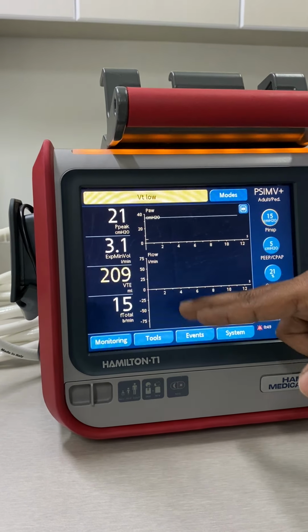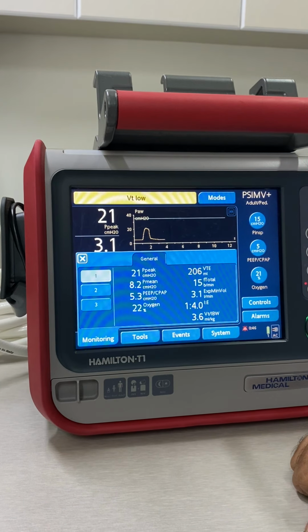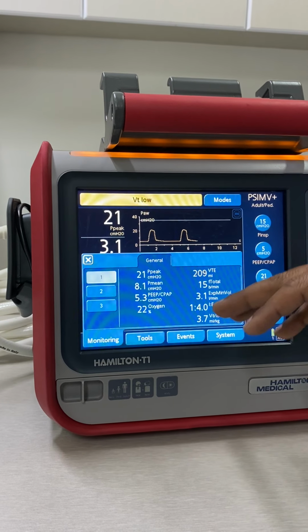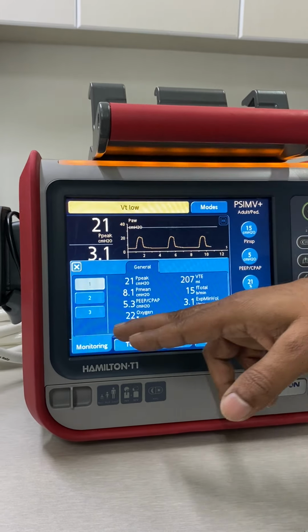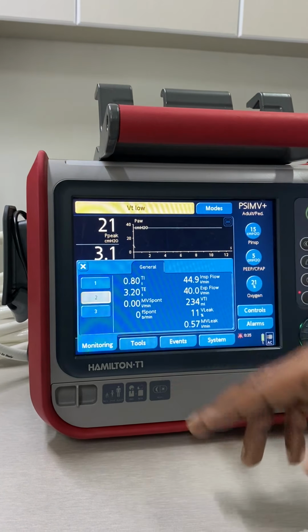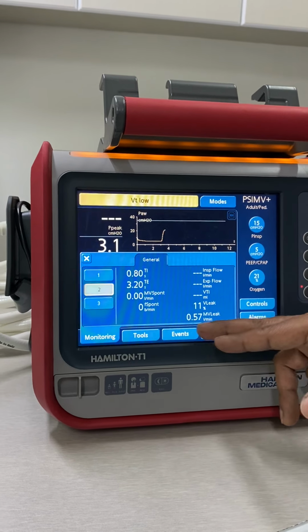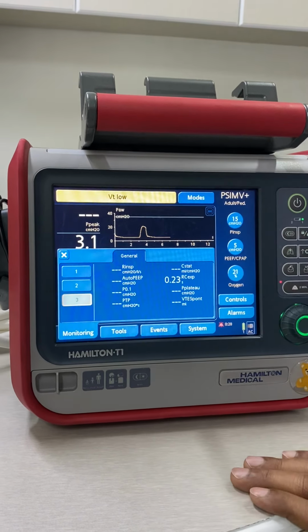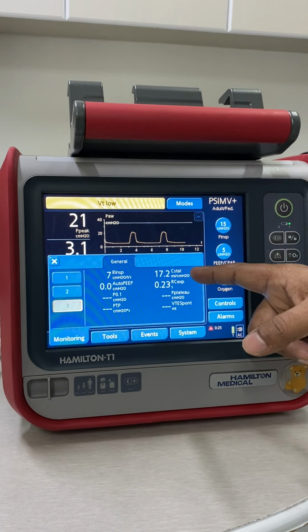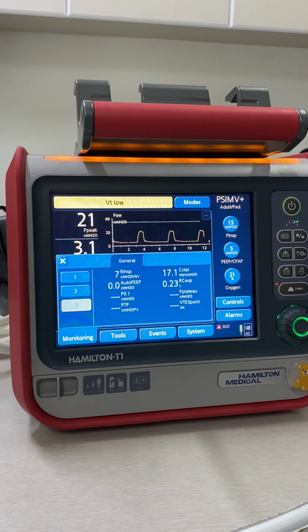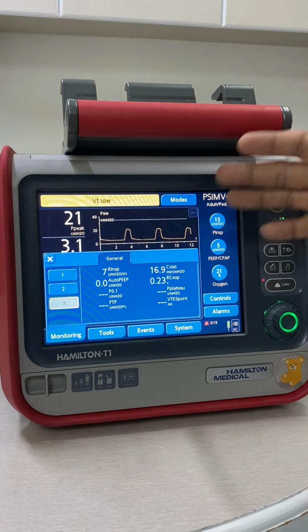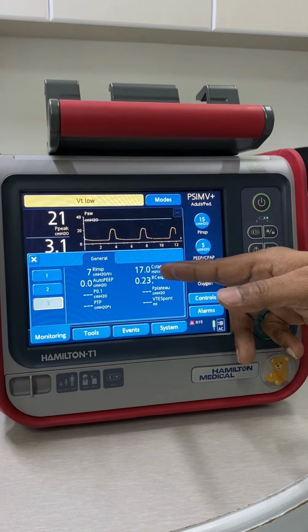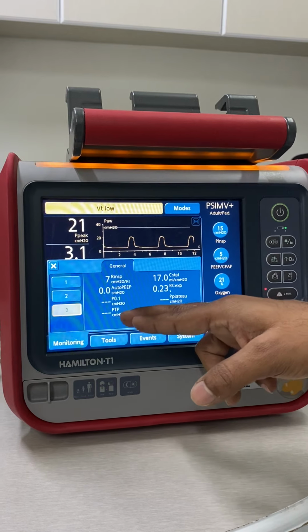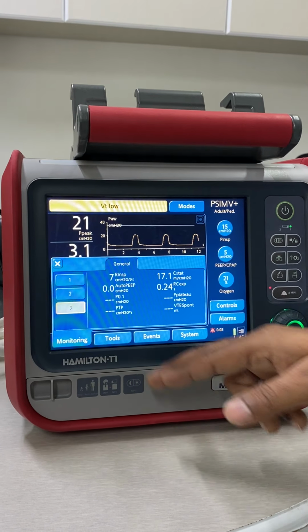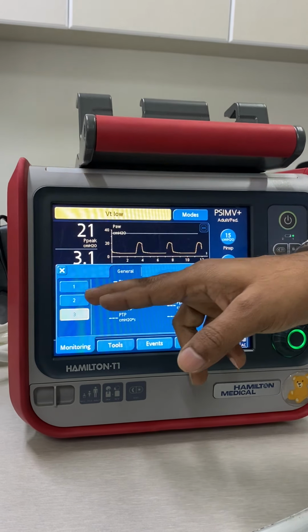So, and also if you want to see more monitorings, if you go to here, we have 3 pages of monitoring like peak pressure, mean pressure, tidal volume and exhaled tidal volume, tidal volume per kilogram, oxygenation. Second page you have the I time, E time, flow, and if there is any leak it will show here, and spontaneous effort of the patient. The third page we have the inspiratory resistance, static compliance, and also we have the expiratory time constant, which will give you what type of lung you have, like restrictive, obstructive or normal lungs. You can easily understand. Plateau pressure will be calculated and monitored here. You have the pressure time product and also the patient occlusion pressure for the patient's activity. So you can have all the monitorings over here, 3 pages. So the complete monitoring is there.